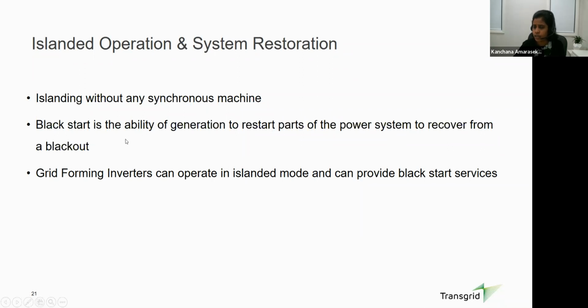And the second item is black start. It is the ability of a generator to restart the power system to recover from a blackout. Usually these services are provided by synchronous machines. Even right now, I think these services are normally provided by synchronous machines, but going forward, it is expected that other emerging technologies like grid forming inverters can provide these services. But as far as I know, at least in Australia, I don't think this capability is tested in the network, but I'm sure it's been tested in environments like microgrids.